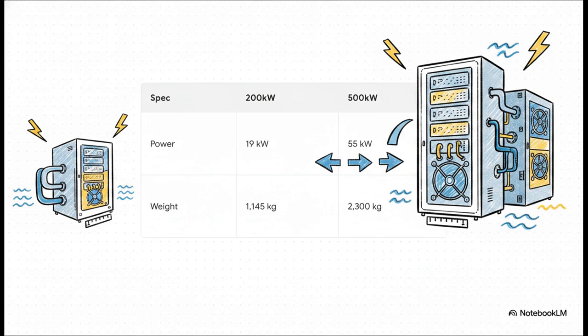Then look at the beast next to it, the 500 kilowatt capacity model. To support that insane cooling threshold, its maximum power consumption jumps to 55 kilowatts, and the dry weight literally doubles to 2,300 kilograms. The physical footprint expands too, the 500 kilowatt model is 2,200 millimeters wide, compared to just 1,100 millimeters for the smaller unit. Make no mistake, these are heavy-duty, serious pieces of enterprise hardware.